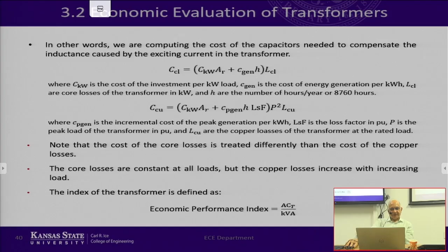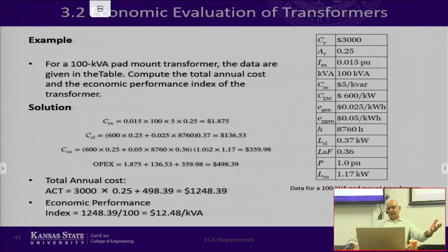The next slide has an example with all the data for the transformer. All we have to do is plug in the values and come up with an answer, which is $12.48 per kVA for the economic performance index. So if you have two different transformers to compare, you can do all the calculations and find out which one is the better transformer.